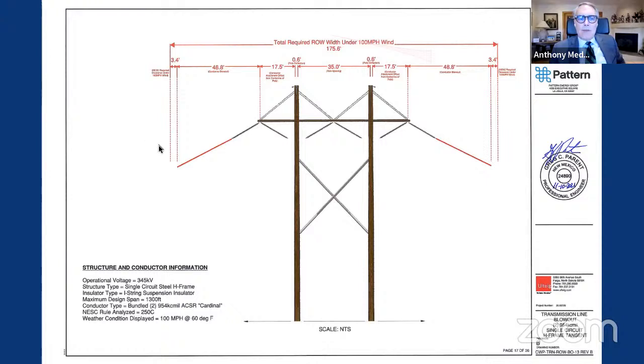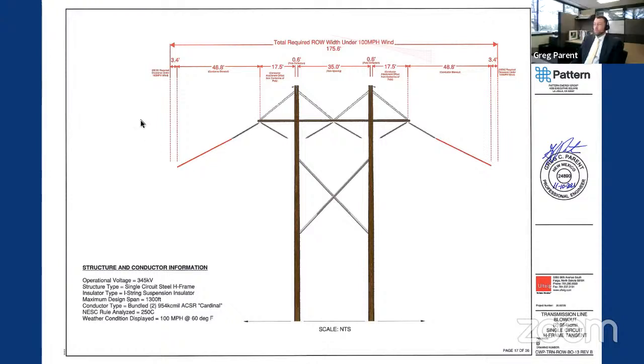That swinging is what's represented here, right? Part of it is the insulator swing—you can see the insulator is what attaches to the structure. And that red line is the sag of the conductor and how much that conductor blows out.